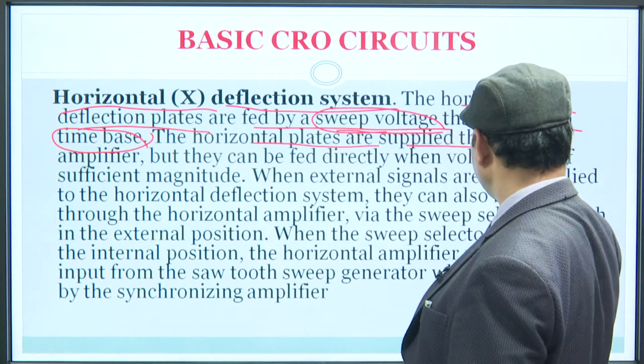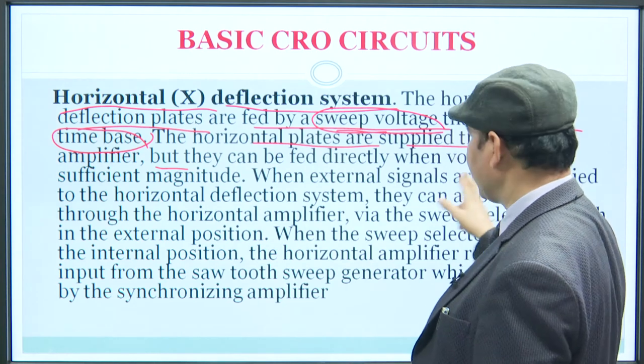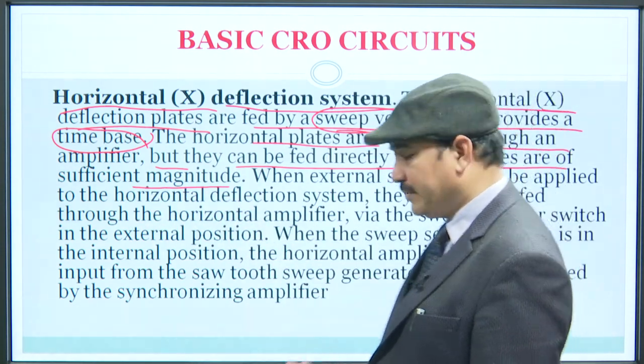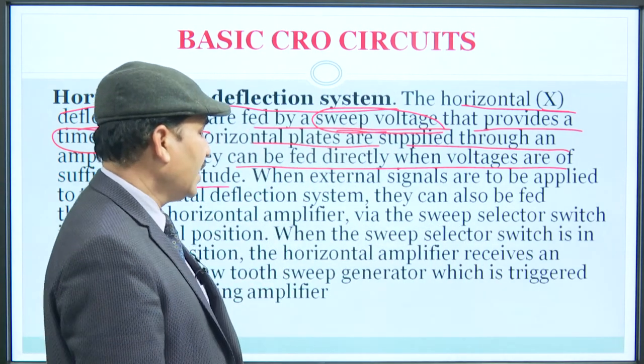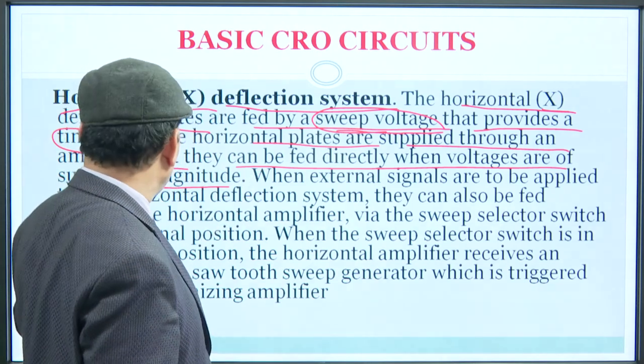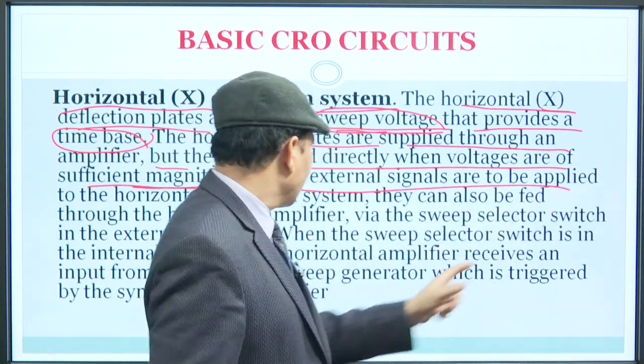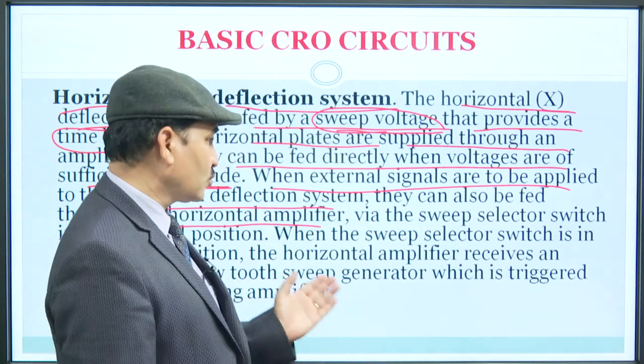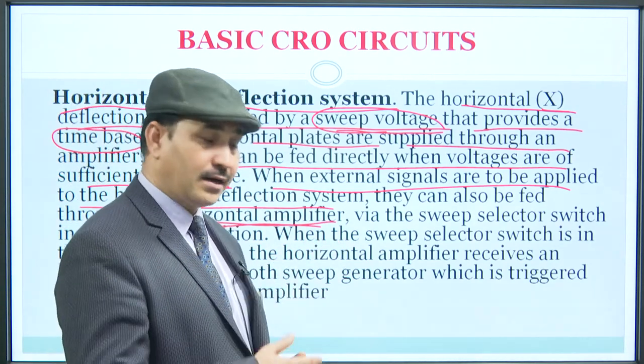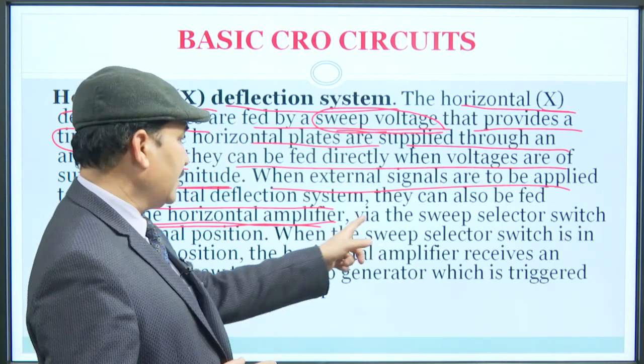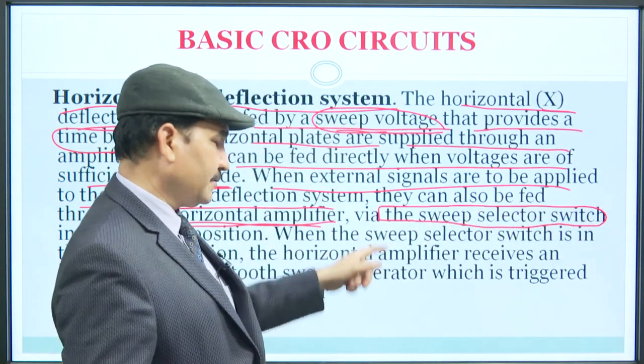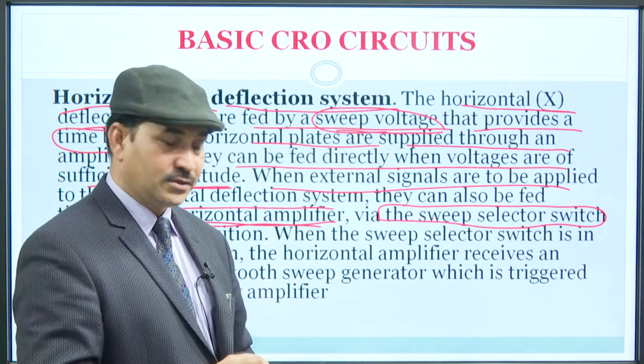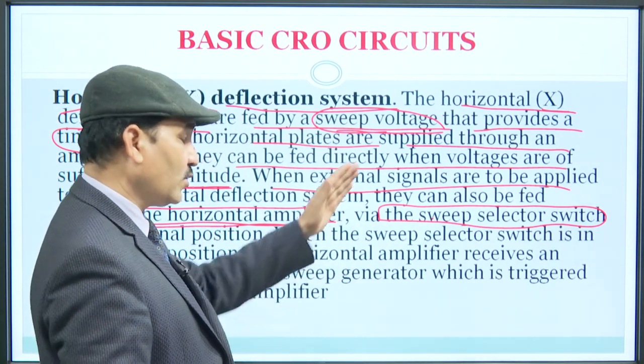The horizontal plates are supported and supplied through an amplifier. These horizontal plates can be fed directly when the voltages are of sufficient magnitude, so attenuation is not necessarily required unless the voltage level is very high. But when external signals are to be applied to the horizontal deflection plate, they are fed through the horizontal amplifier. With the help of a sweep selector switch, a part of the input signal is also given to the horizontal plates through the sweep selector switch.